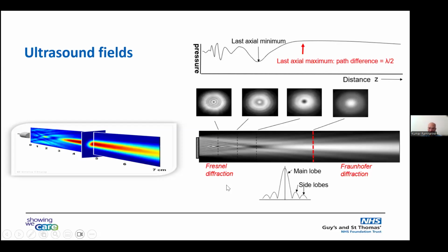What you might notice is that in the near field, if you scan across the beam, you have multiple high amplitude and low amplitude areas. Why is this? What is causing this pattern? Also you have these side lobes. You have a main beam, and then you have side lobes, which are emitted at an angle to the main beam. And this becomes important for certain artifacts.